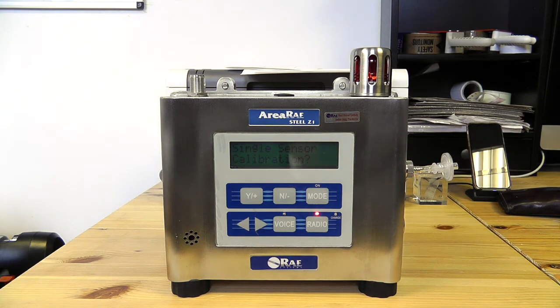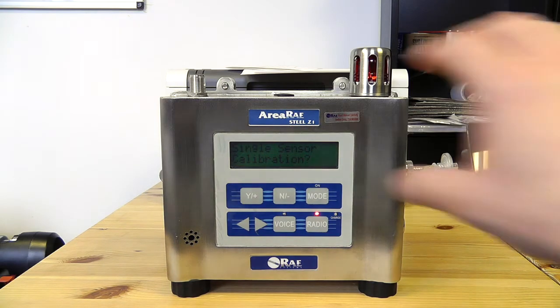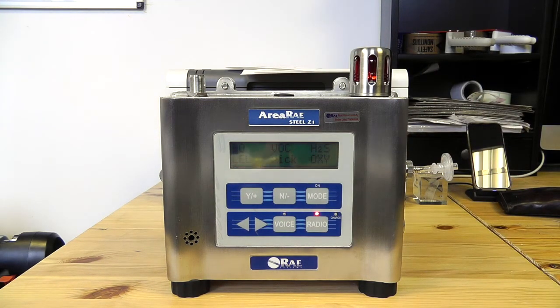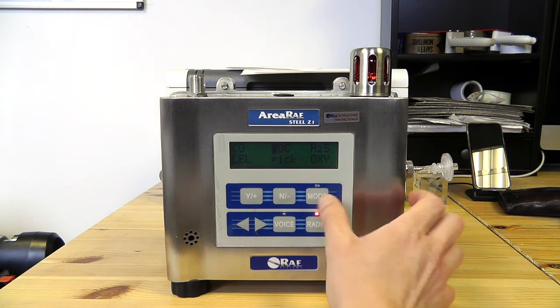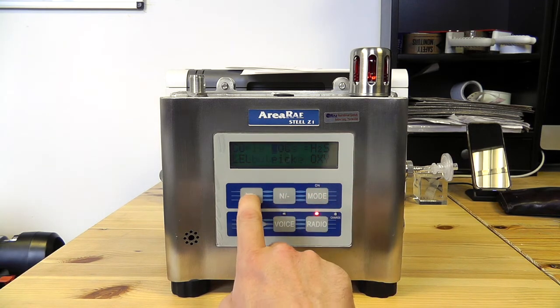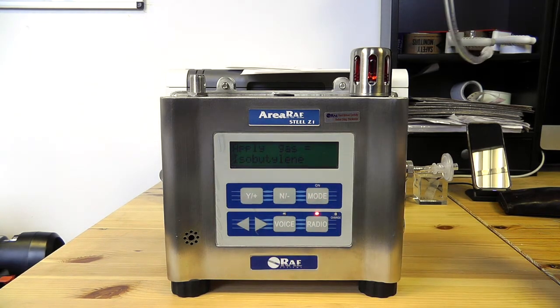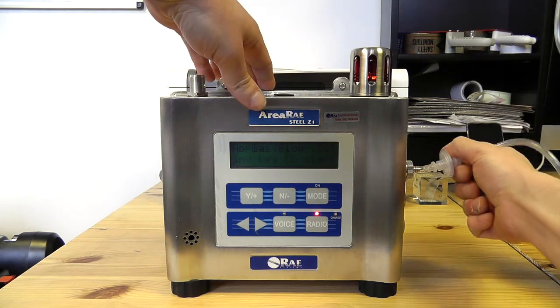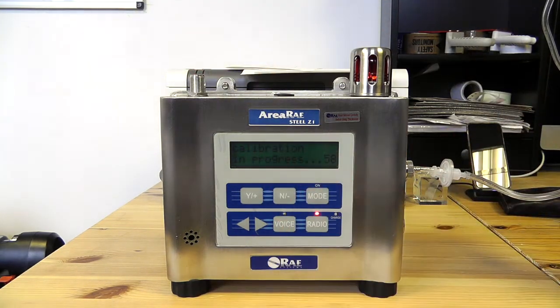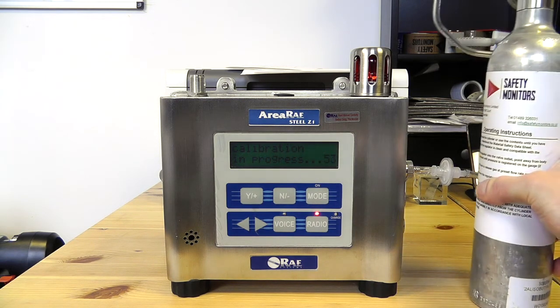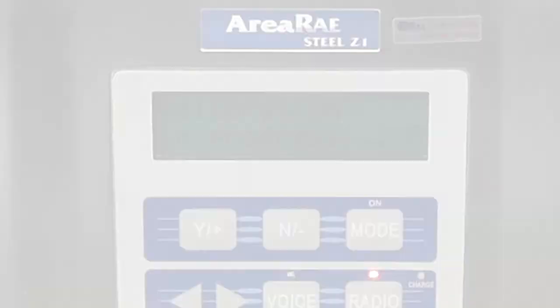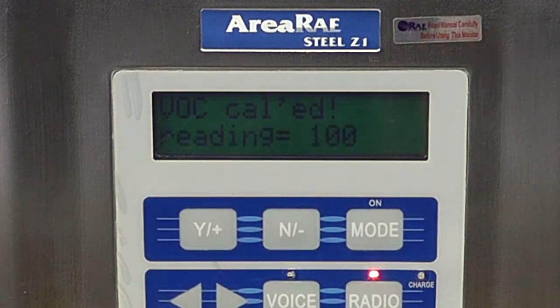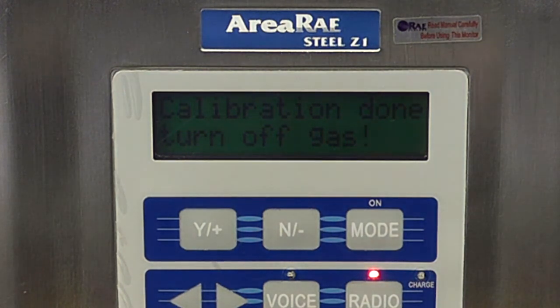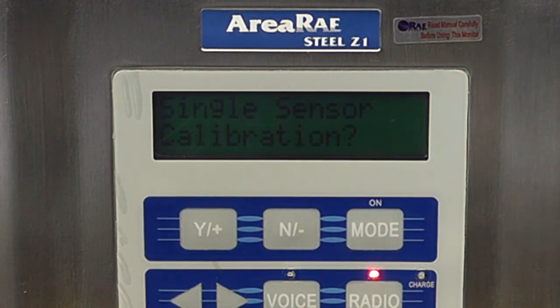So I will simply take a 100 ppm can of isobutylene. Yes, we want to do a single sensor calibration, and we pick which sensor we particularly want to calibrate. So in this case, no, we don't want to do that, we want to hit the VOCs, so hit yes, and then it'll ask us to apply gas. So we'll apply 100 ppm. As soon as the gas is recognised as flowing, it will take another 60-second calibration to calibrate the VOC sensor. So we can see the VOC has been calibrated to 100 ppm, so we can now remove our gas flow from the end of the device.